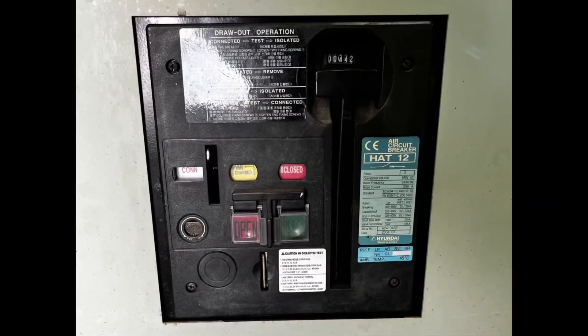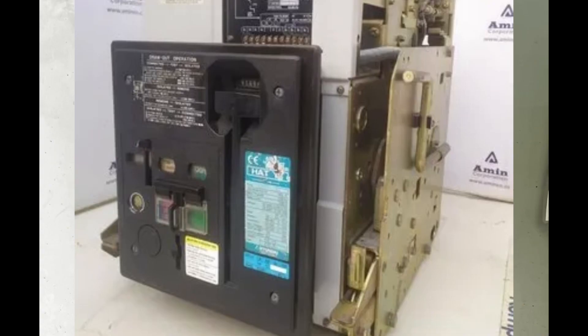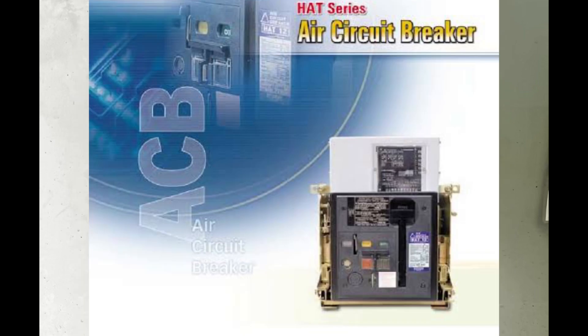Hello guys, welcome back to my YouTube channel. In this video I am going to show you how to change the UVT device from a Hyundai HAT series ACB. As you all know, UVT is a device which makes the ACB trip automatically to prevent accidents on the load side.